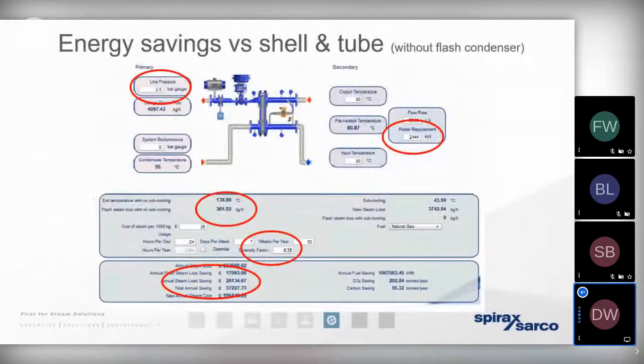So I just want to remind us that by moving away from that storage solution towards a typical plate heat exchanger that's generating hot water from steam instantly, we're going to get a significant number of energy saving, cost saving benefits. And part of this goes back to the first principles that we've already covered. Steam's a gas, gives up its heat energy evenly. So we've got an efficient use of the heat transfer surface area by having a greater number of plates.